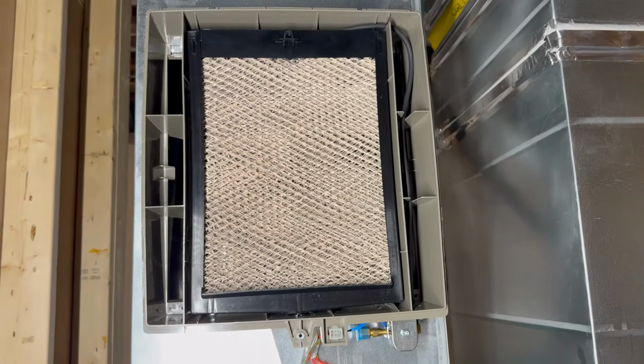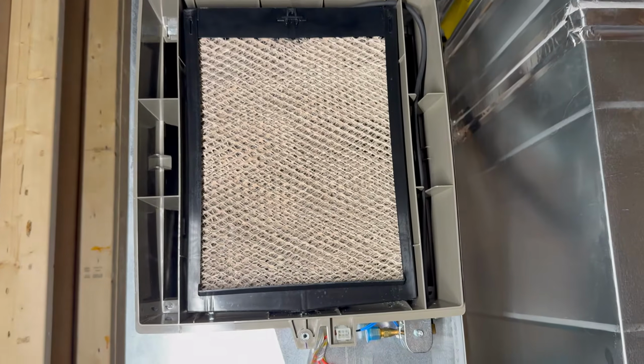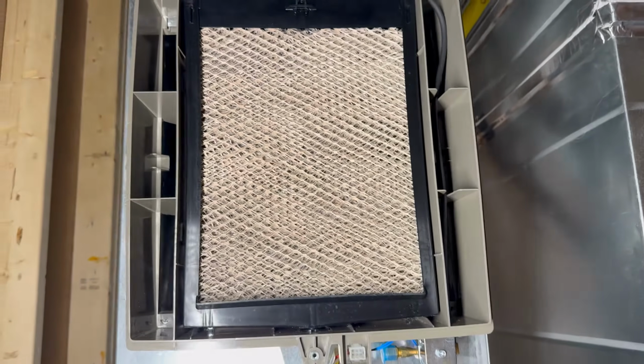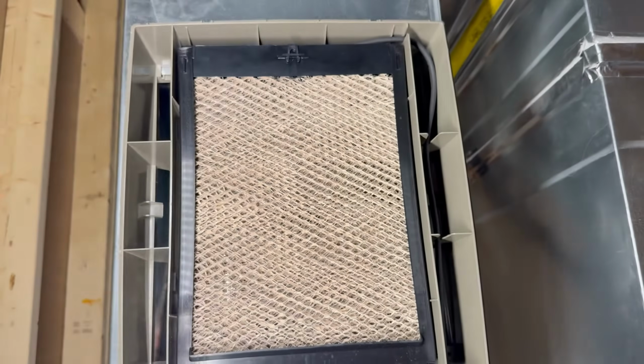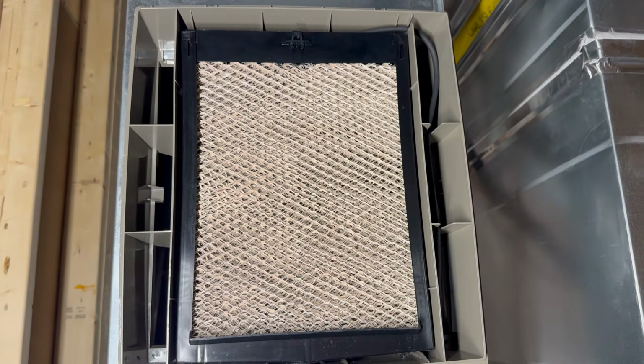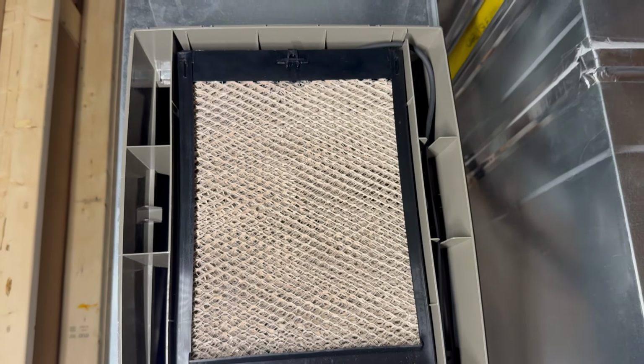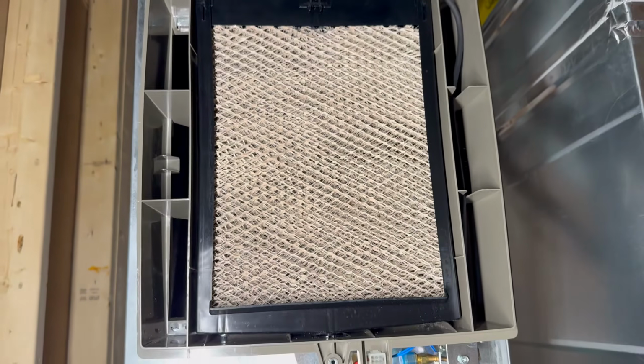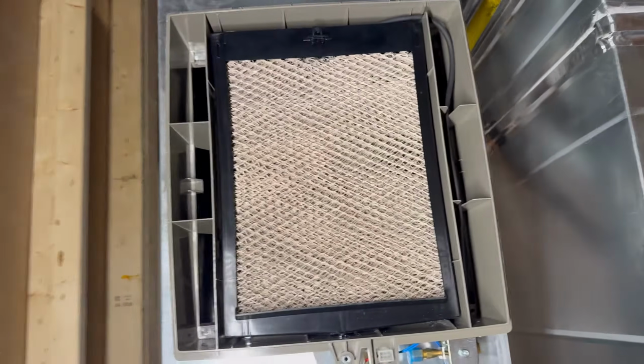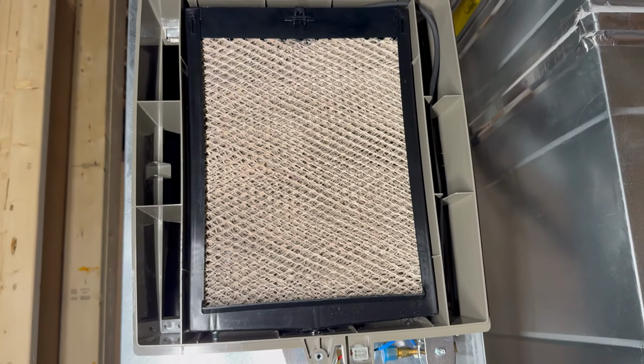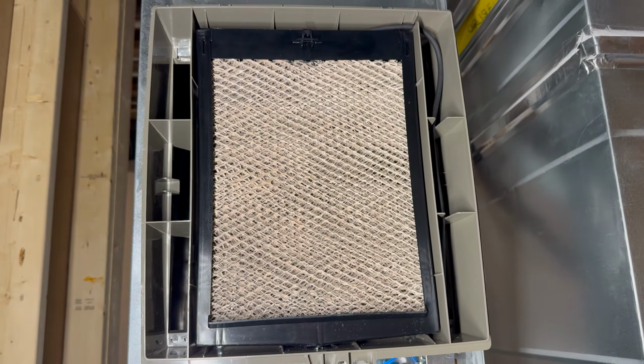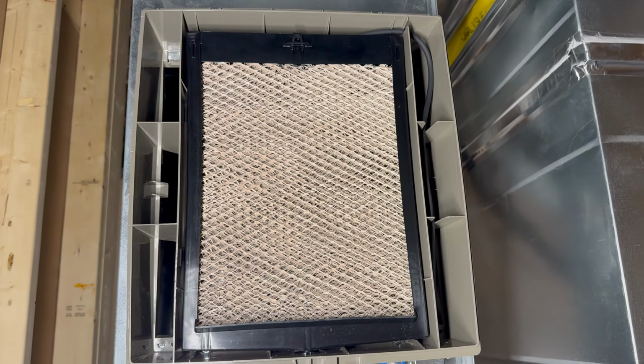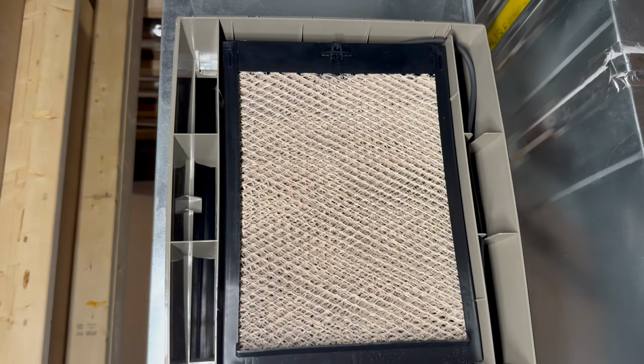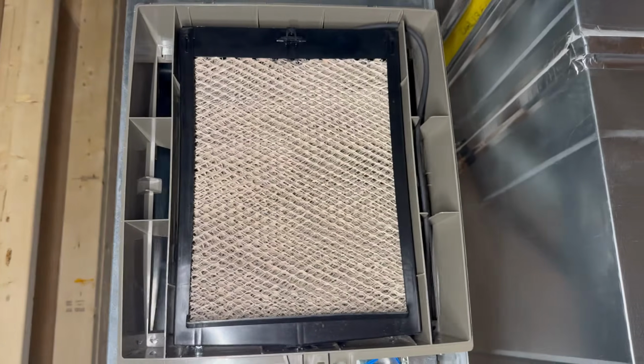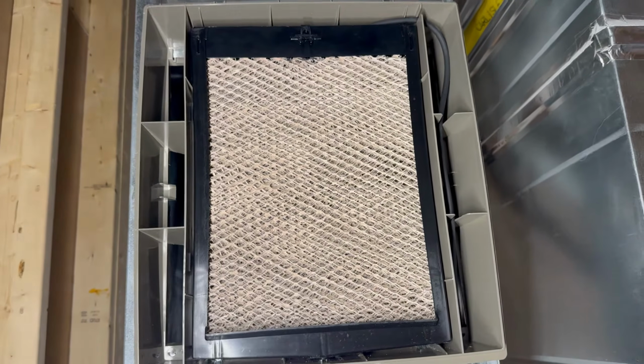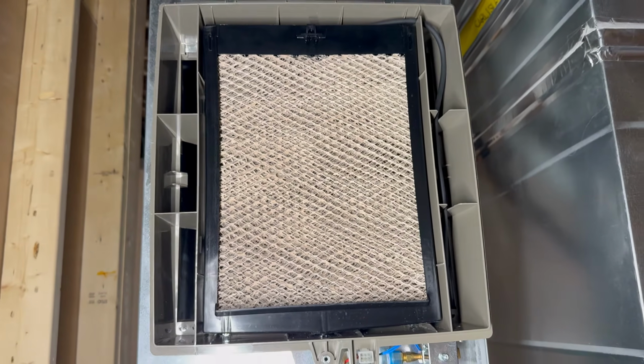And I know many of you are asking, if this isn't perfectly level, is it going to be an issue? And the answer is yes, because when the water flows, it trickles down this pad evenly. If it's not level, the water is going to accumulate on one side and you're not going to have perfect distribution. And you could also have a leak. If you have too much water on one side of the pad, at the top, if it's not draining fast enough, it could leak down the actual housing and then drain into your furnace, which is not what you want. So you want to ensure this is perfectly level.